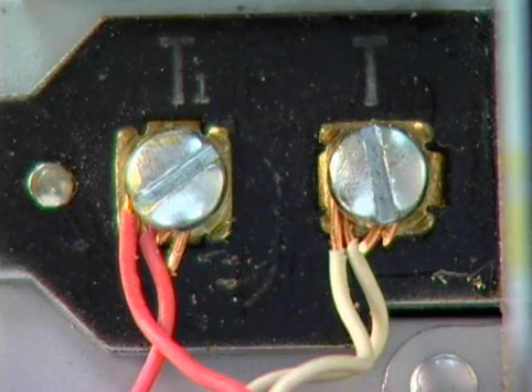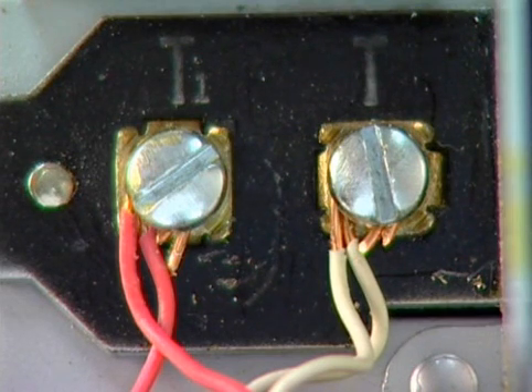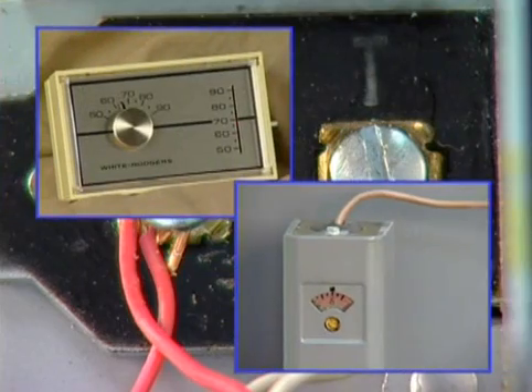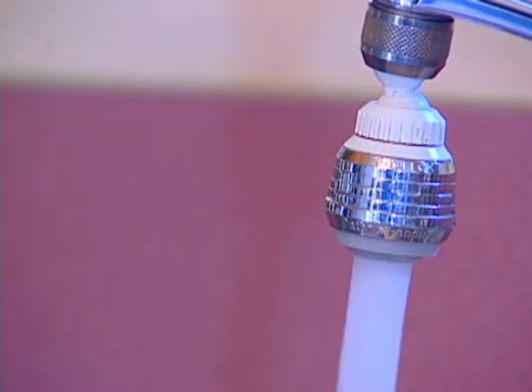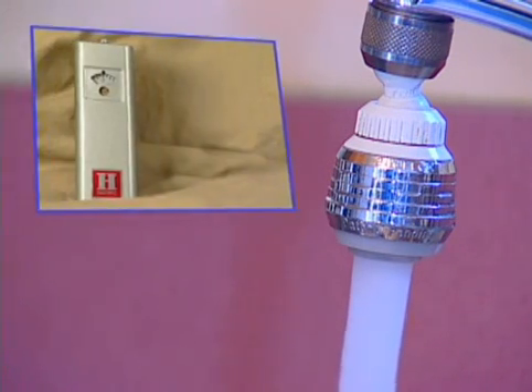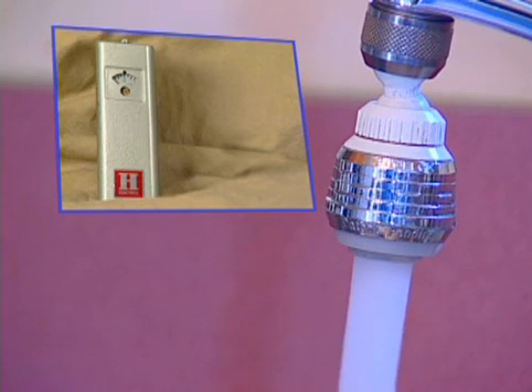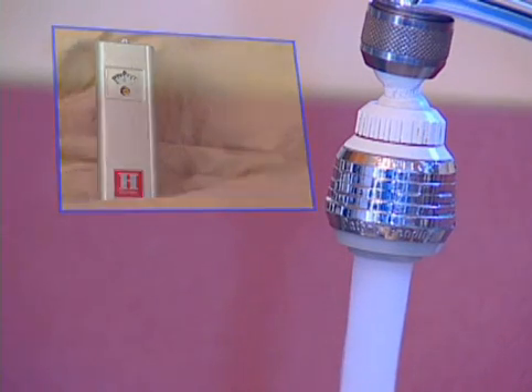Some systems have an additional control wired in parallel with the thermostat. In those cases, the primary's low voltage circuit can be completed through either the thermostat or that additional control. For example, a steam boiler with a domestic hot water coil installed normally has an aquastat wired to the low voltage terminals. This enables the boiler to maintain domestic hot water even when the thermostat is not calling for heat.